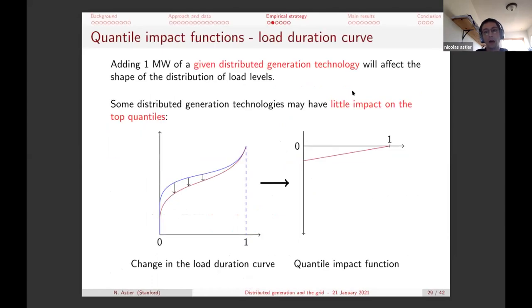And so having assembled this data set, what we are interested in is assessing the impact that adding a megawatt of a given technology has had on average on the load curve and ramp duration curve seen by the substations. So if I get back to my example, you have a historical load duration curve, you add distributed generation and it shifted down. So what we're trying to estimate is basically the difference between these two curves.